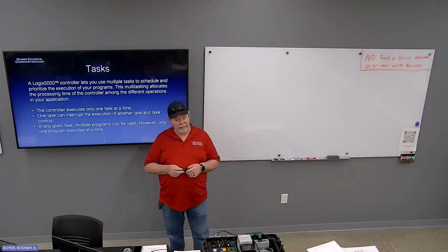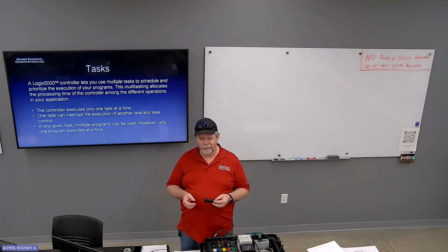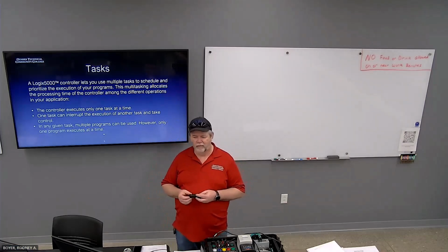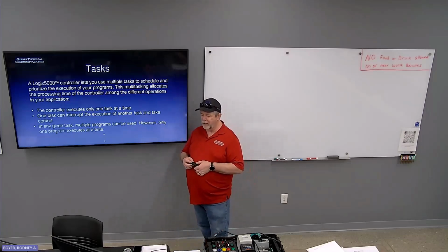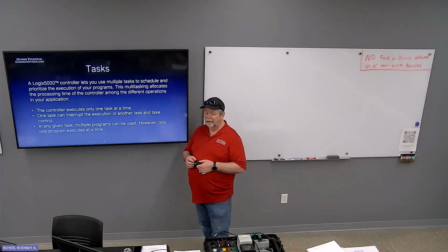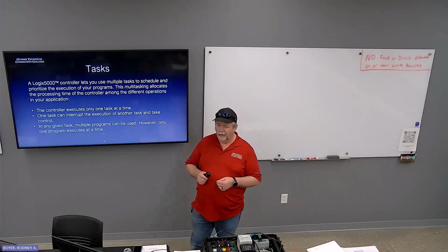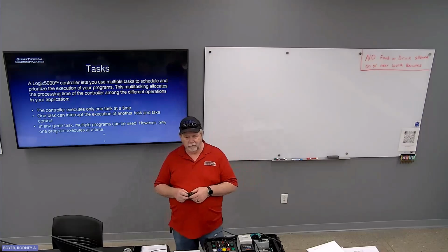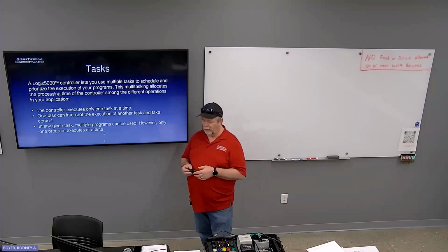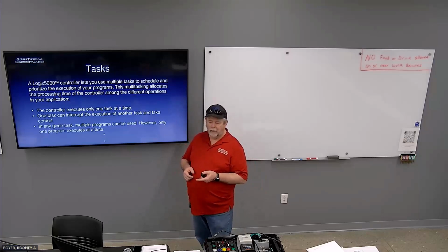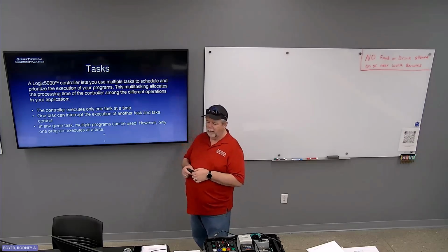How can they be multitasking when it only executes one at a time? That just doesn't jive. Okay. One task can interrupt the execution of another task and take control. If you have multiple tasks, you have to assign them priority. Okay. In any given task, multiple programs can be used, however, only one program executes at a time. It does everything one at a time. It just does it really fast. It looks like it's multitasking.